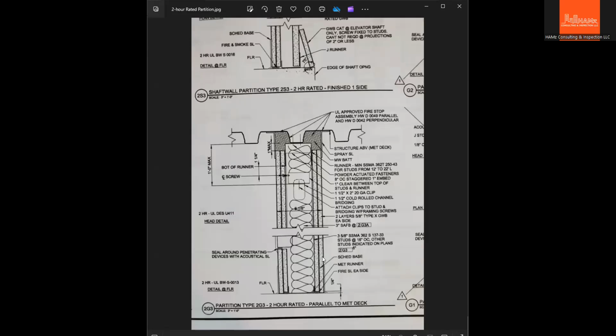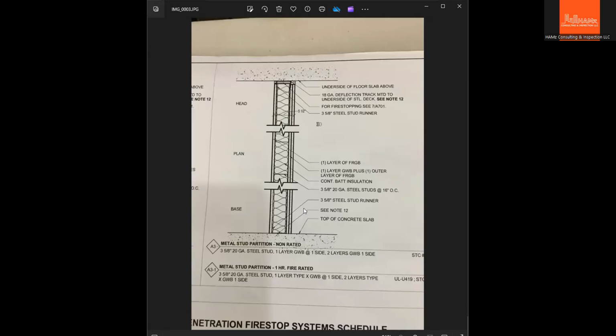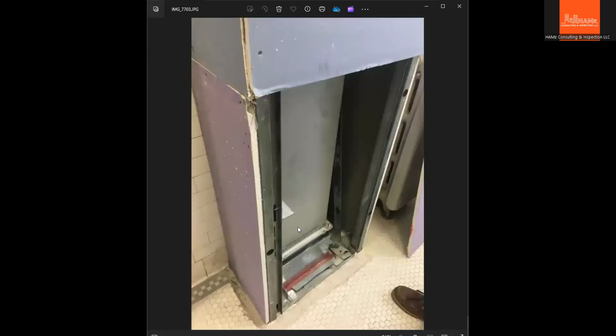So this is one of the details. Another detail right here, this is also an enclosure. This is a 2-hour rated installation detail. So 2 layers of 5/8 on both sides of the studs. This is an alternative. You could see this in rated walls also. Other details. So this is an example of the installation. This is an enclosure for a duct. Because the duct penetrates a floor or a ceiling, you need to isolate that rating by building an enclosure like this. So this should be 2 layers right here and 2 layers on the inside, both sides of the framing or the stud.